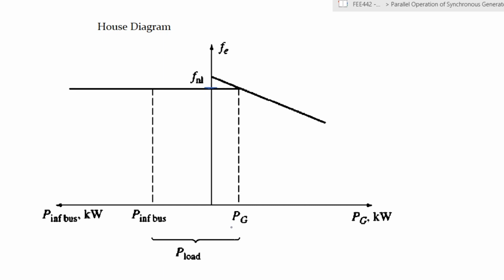So in case your generator is supplying power to the infinite bus bar at that level, and you want it to supply at a new level here, call it PG2, let's call it P2, the droop characteristic will not allow it to match. Here is where your generator wants to be, but the frequency of your system is over there. So in order for you to match the two, you have to see at which point you want to supply.